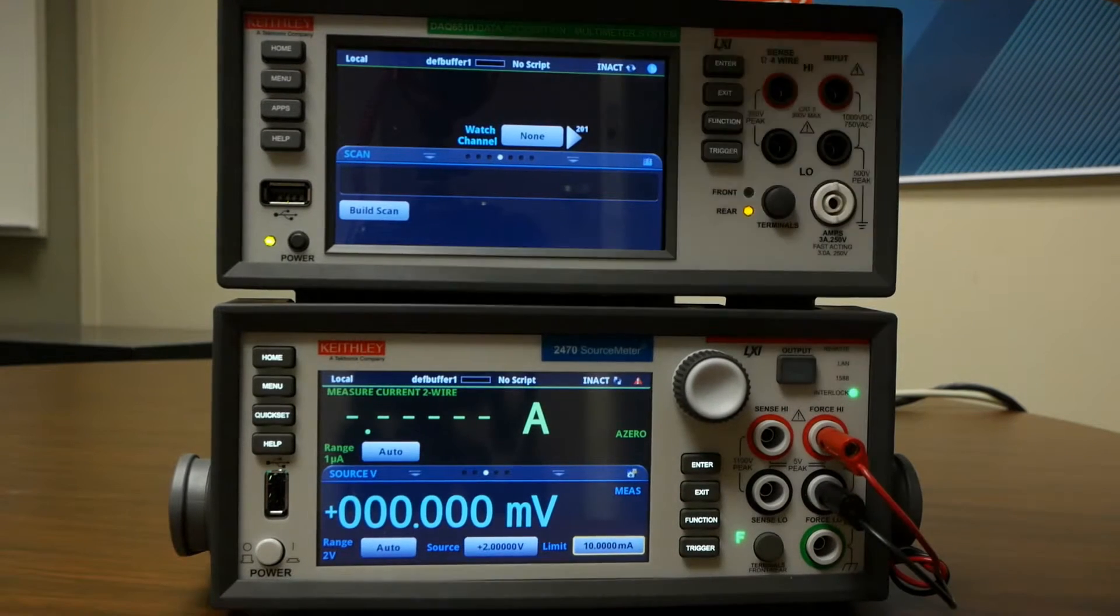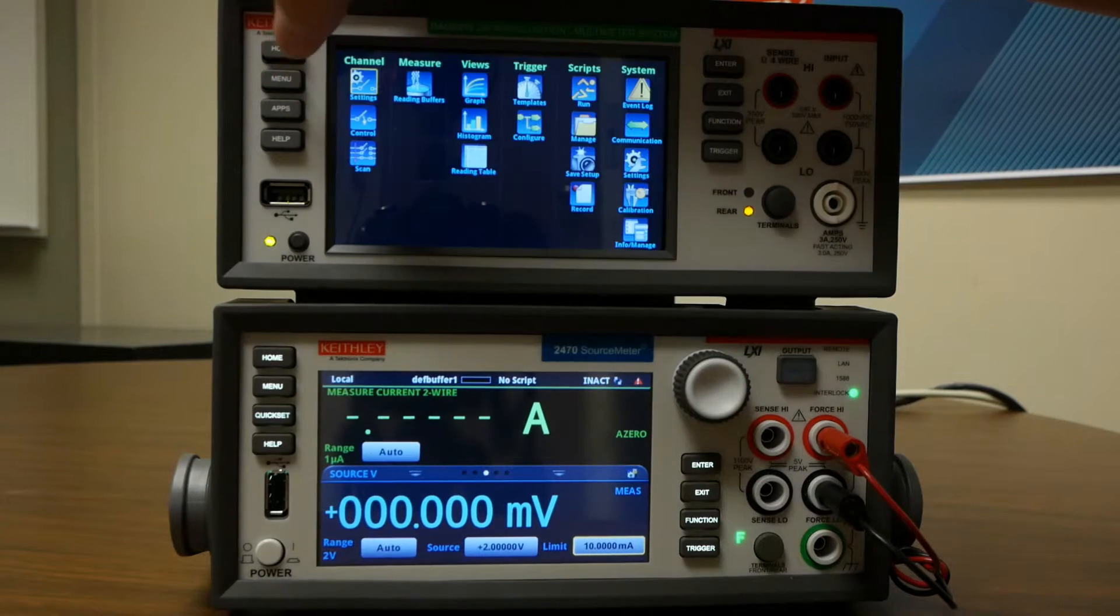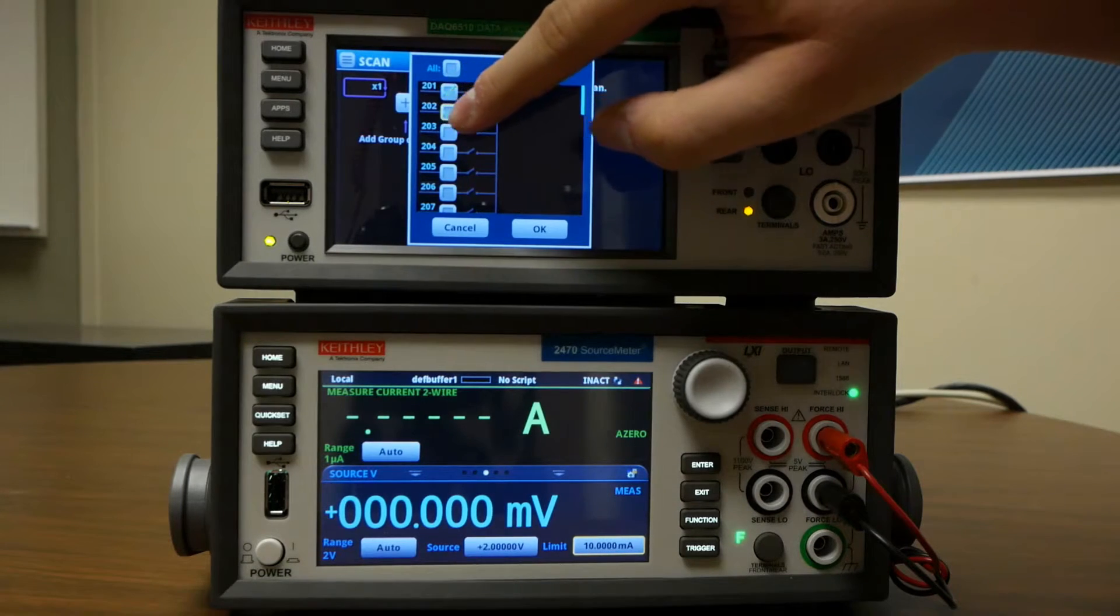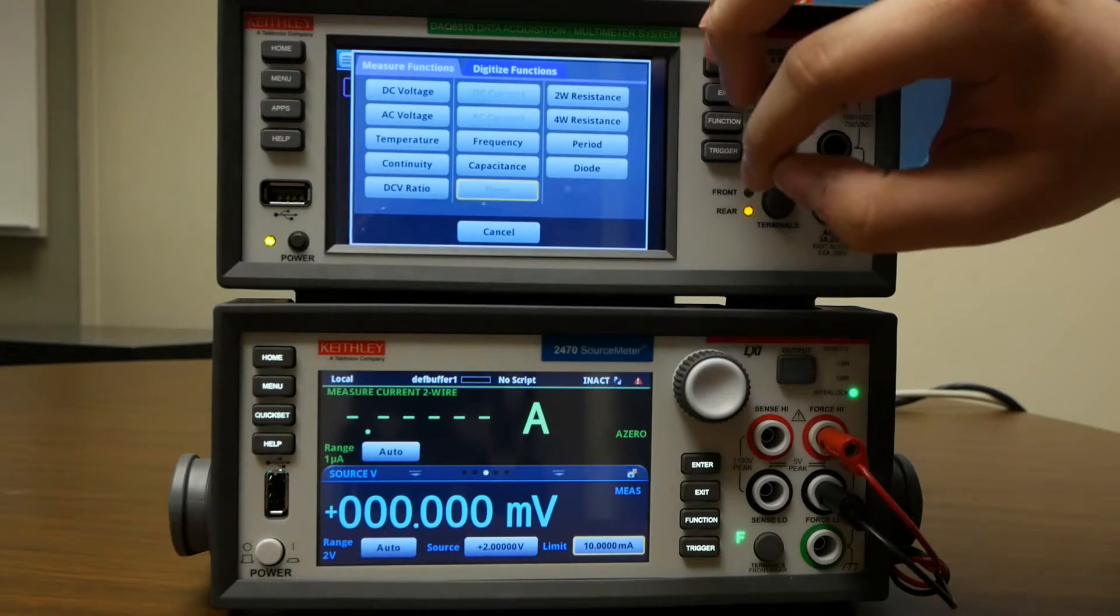We'll go to the DAQ6510. We're going to start by pressing the menu button. Under channel, go down to scan. We're going to add our channels. Our devices are in channels one through three. Press OK. And we'll just have it monitor voltage.